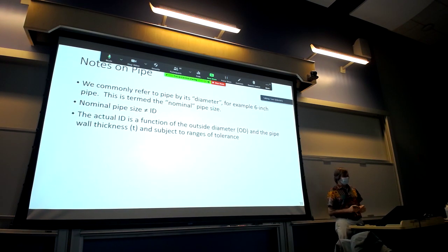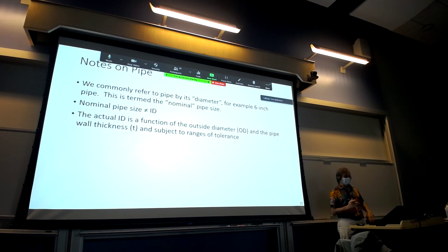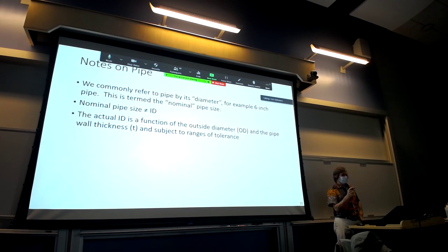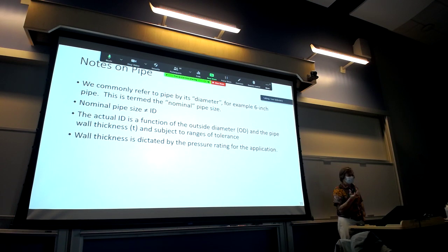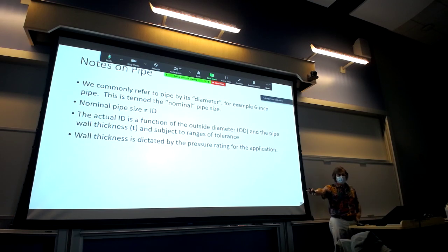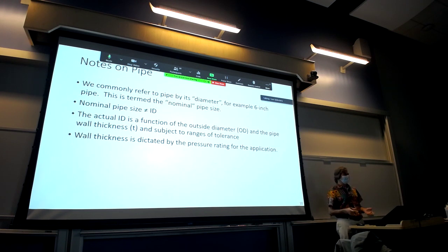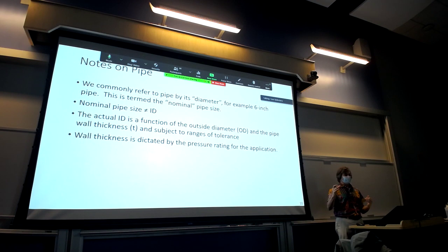The wall thickness is dictated by the pressure rating — the thicker the wall, the higher the pressure rating the pipe can withstand. If you take the outside diameter and subtract twice the wall thickness, that may or may not equal the inside diameter due to tolerances. In household systems, working pressure is typically 40 to 60 PSI — you don't need pipe rated at 500 PSI for your house.